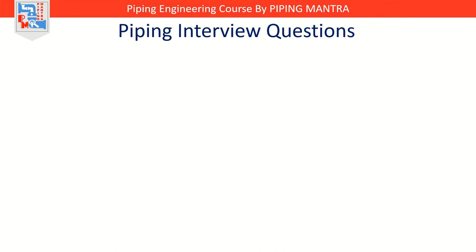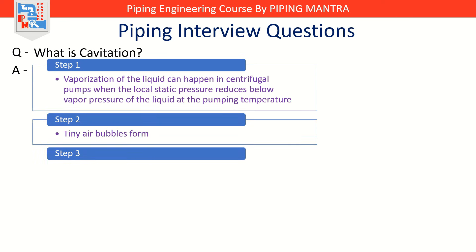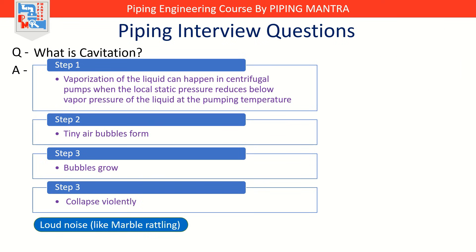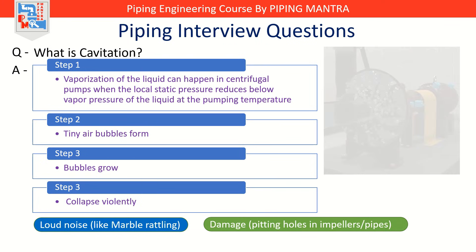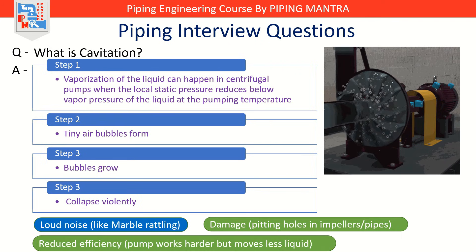Let's move into a problem every pump engineer fears — cavitation. What exactly is cavitation? Cavitation happens when a liquid in a pump vaporizes because the local pressure drops below its vapor pressure. It's like when you try to suck a thick milkshake through a straw but the straw isn't fully in the shake — you get pockets of air. In pumps, these pockets are vapor bubbles. They form, grow, and then collapse violently. This causes loud noises — sounds like marbles rattling inside — damage such as pitting and erosion on impellers and casing, and loss of efficiency where the pump works harder but moves less liquid.